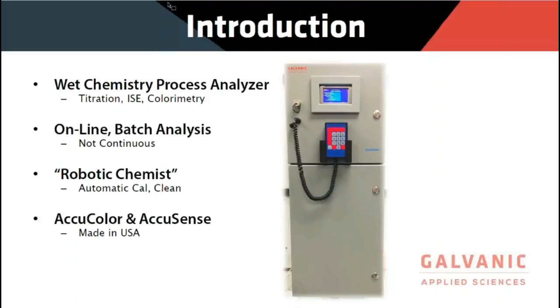AccuSeries is a wet chemistry process analyzer, and it can be configured to perform titrations, ISEs, and colorimetric analyses. It's an online analyzer, but it's not a continuous measurement, it's a batch analysis. And we do this in order to conserve reagents, to save on costs, as well as different analyses require some time before the result is given.